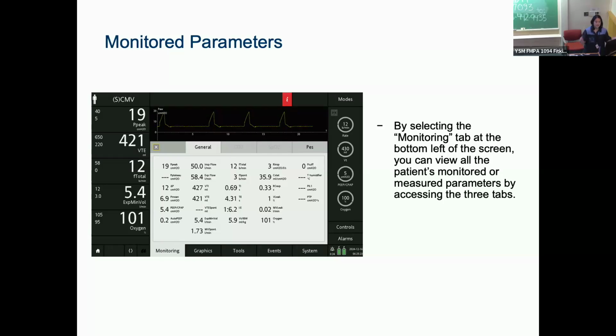And that we should actually check a plateau pressure and calculate the real number, which the RT will do. And that is the number that's recorded in Epic. So when you're looking at Epic, you have actual respiratory therapists validating a number which they've measured. Whereas if you're just looking at the ventilator, these numbers are approximations from this microocclusion during the breath.